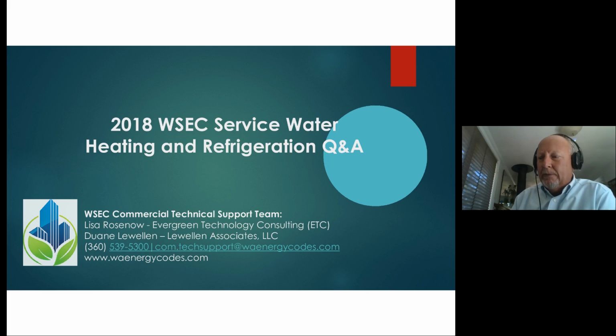The other thing to keep in mind is that demand response generally is a relatively short-term event, an hour or less. So the water heater, or the heating elements anyway, are not going to be turned off or overridden for a very long time. Given the current installation requirements for water heaters, I don't see a lot of losses occurring. But if there is a conflict, then other codes would supersede the energy code, whether that's a plumbing code issue, a building code issue, or some other health and standard code. That would take precedence over the energy code standard. Yeah, that's a great point.